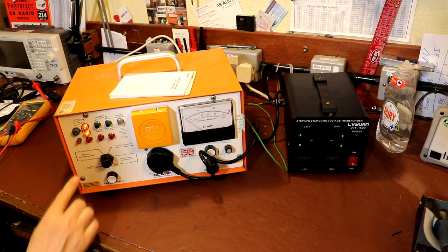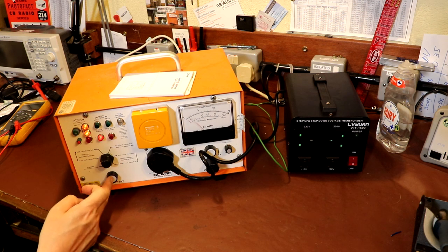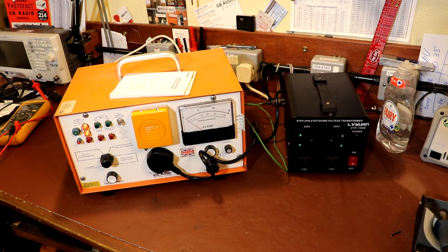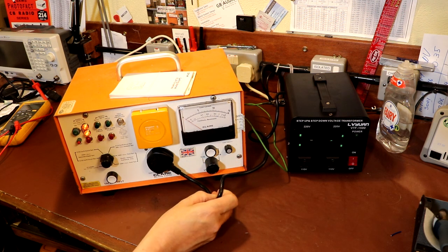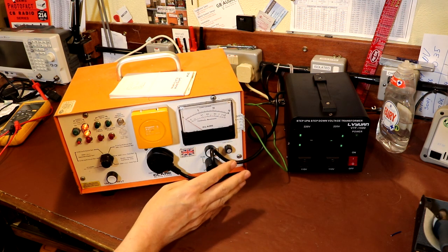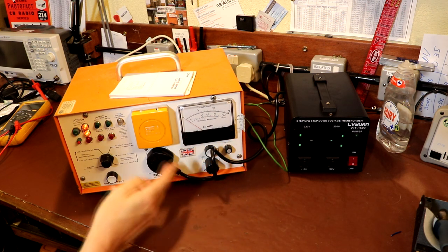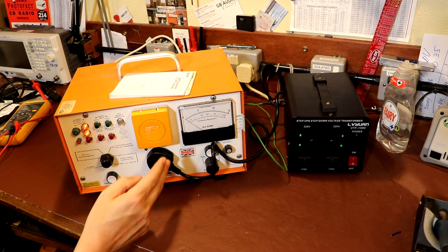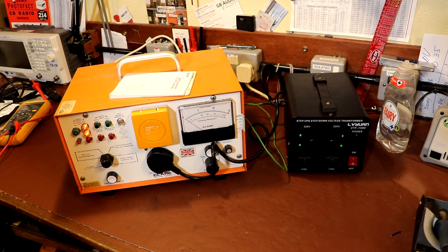And let's try the higher test here. So we're now at 1250 volts and 0.1 ohm, and it passes that too. So we can be fairly confident here that the insulation is good on our transformer, and that we do have a really good earth connection between the outer case of the piece of equipment and the earth wire back to our plug socket. So if we get a fault, it should trip the circuit breaker or blow the fuse in our plug, and we will be protected.